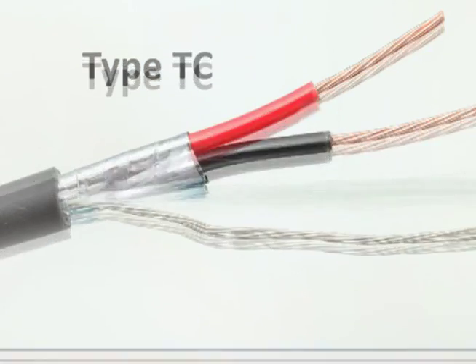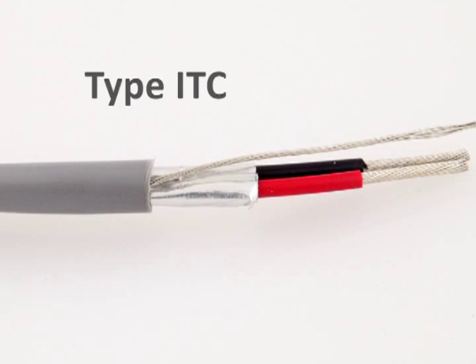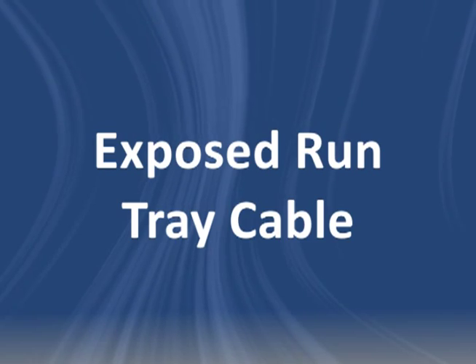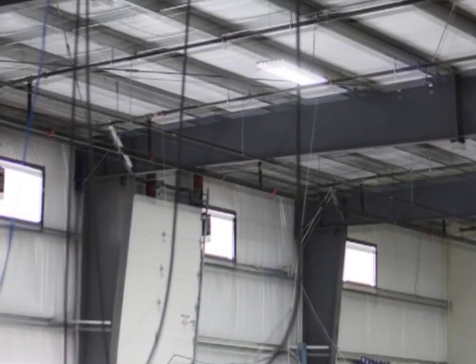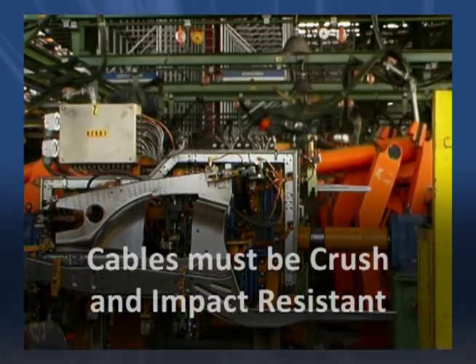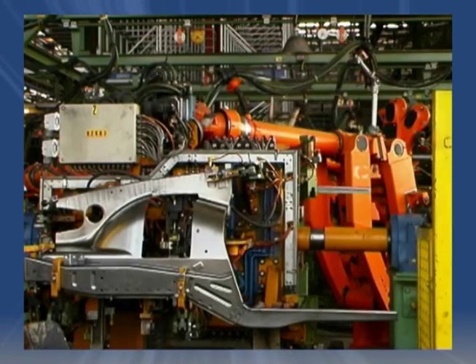The ER Tray Cable Rating can be applied to Type TC, Type PLTC, or Type ITC Power and Control Cabling. ER stands for Exposed Run and means the cable can be used as open wiring in industrial environments without the protection of a cable tray. UL requires that these cables meet extra crush and impact testing requirements to achieve that ER rating.